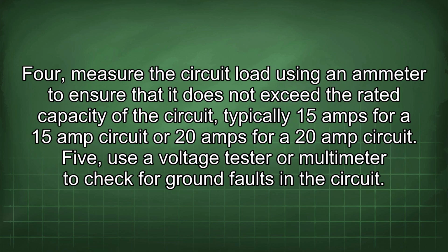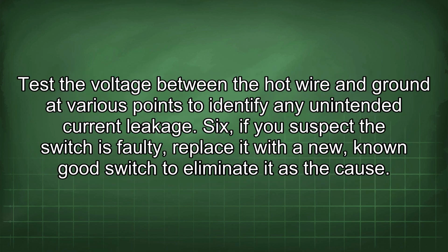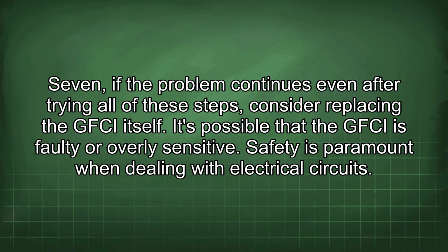4. Measure the circuit load using an ammeter to ensure that it does not exceed the rated capacity of the circuit, typically 15 amps for a 15 amp circuit or 20 amps for a 20 amp circuit. 5. Use a voltage tester or multimeter to check for ground faults in the circuit. Test the voltage between the hot wire and ground at various points to identify any unintended current leakage. 6. If you suspect the switch is faulty, replace it with a new, known good switch to eliminate it as the cause. 7. If the problem continues even after trying all of these steps, consider replacing the GFCI itself. It's possible that the GFCI is faulty or overly sensitive.